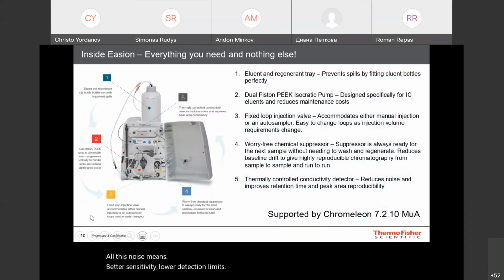So how does it look inside? Small IC, but the best design of the pump and pump heads. It's a dual piston, so the pump is 2 pistons, and they are working in series. So it's similar to HPLC, just inert again, PEEK coating of the pump heads and pistons.